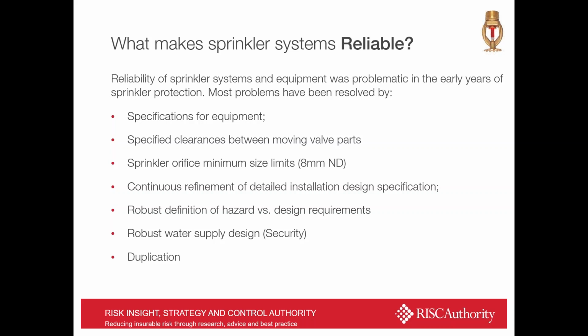but most problems have now been resolved by specifications for equipment, specified clearances between moving valve parts. It's often a criticism that sprinkler systems look like Victorian architecture, but it's with good reason. That actually brings resilience into their whole operation. Size limits, minimum size limits on various orifices, and that overcomes a lot of the water quality problems that we have. But 8 millimeters, these are quite large orifice sizes. Continuous refinement of how we design systems and install them. And certainly RISCAuthority alone spends hundreds of thousands of pounds trying to refine our rules to maintain this level of reliability of the systems. They have good specifications of how to design against a range of hazards, and water supplies are very secure, reliable, and incorporate duplication also.